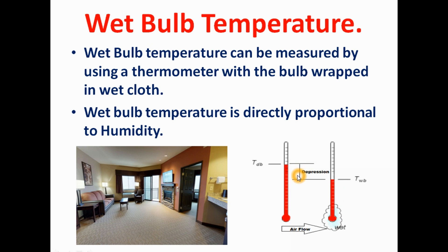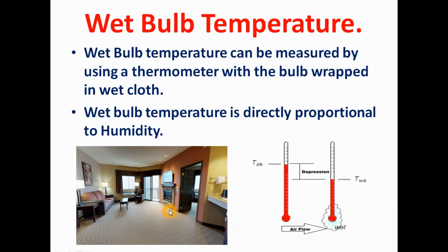This difference between dry bulb temperature and wet bulb temperature is called depression. Suppose we measure the dry bulb temperature of a room and it is 32 degrees Celsius. If we then measure the wet bulb temperature using the same thermometer with the bulb wrapped in wet cloth, the temperature will be less than the dry bulb temperature — this difference is called depression. This depression depends on the humidity of the area: if humidity is more, the temperature difference is less; if humidity is less, the temperature difference is more.